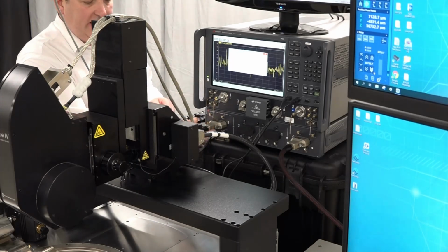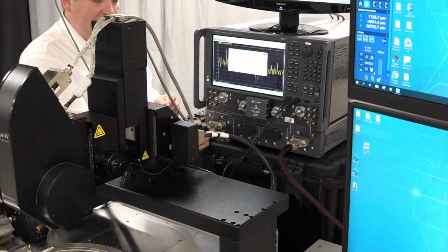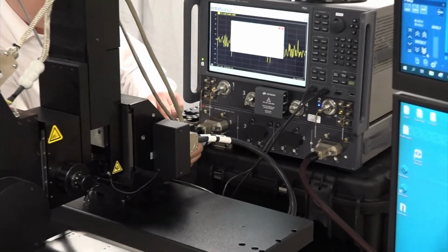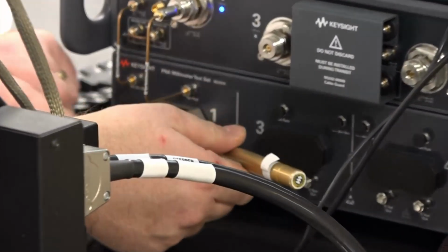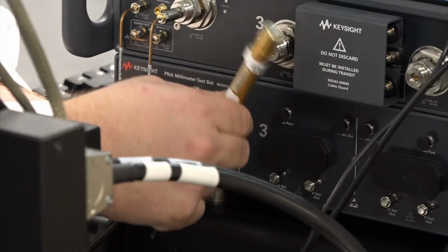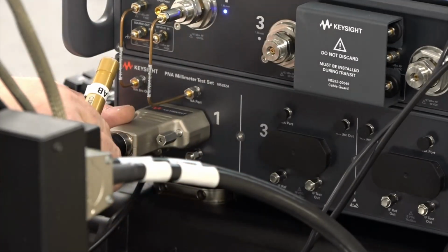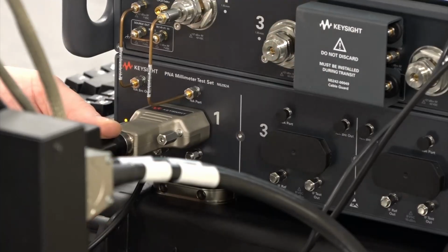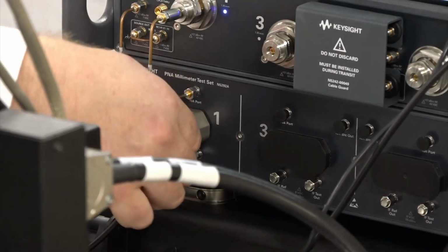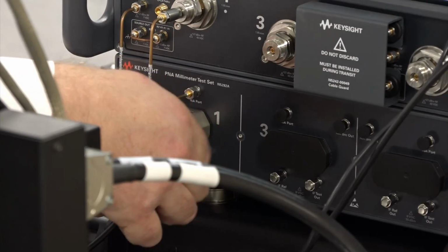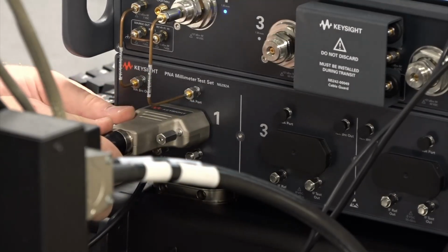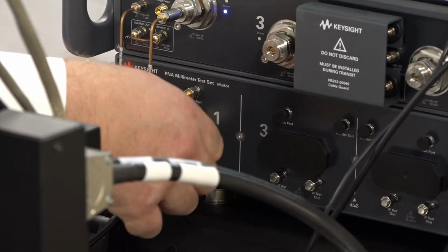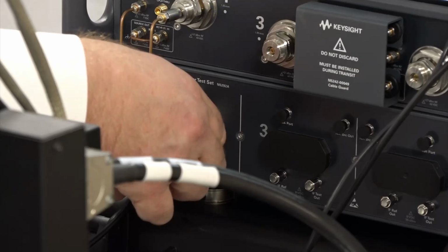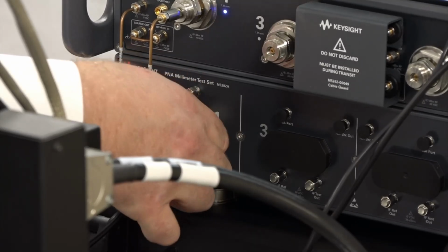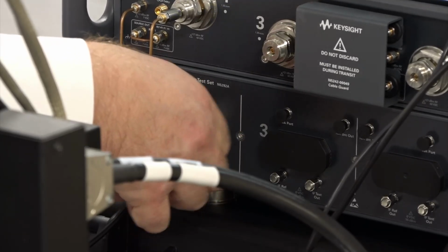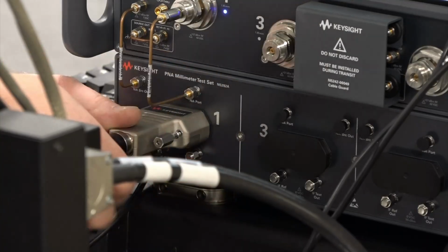These screws that hold the connector for the frequency extender in place will fit a torque wrench, and so typically I always torque these up. I also make sure that I have it pushed in nice and straight. I don't want anything pulling to one side. They're kind of stiff. And just try to undo the screws evenly. You shouldn't need to use a torque wrench all the way out. Generally, it's a way of telling you that something is crooked.